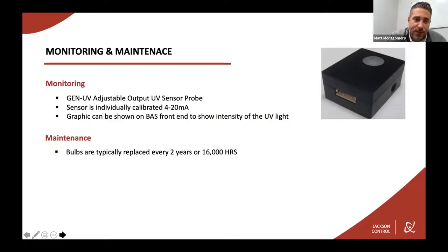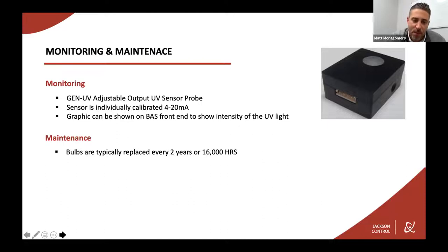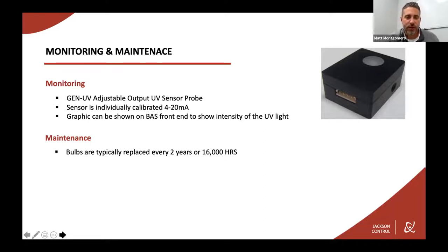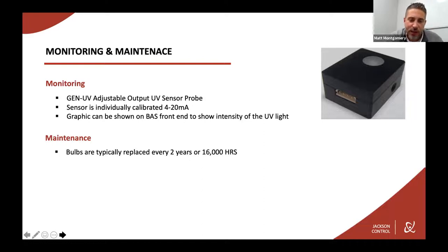Beyond deploying UVC, there's monitoring and maintenance. We have a device called the GenUV where we can monitor the intensity of the UV light and bring it into a BAS front end to display a graphic on UV light intensity for maintenance purposes. The sensors are individually calibrated for 4 to 20 milliamps. Regarding regular maintenance, the bulbs are typically replaced every two years or 16,000 to 18,000 hours, though that varies by manufacturer.